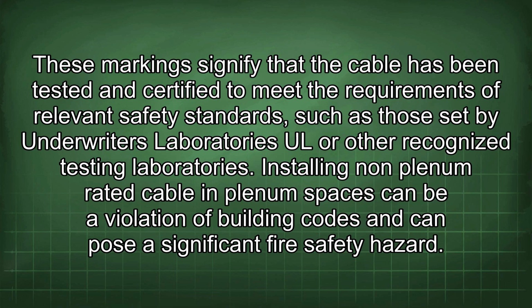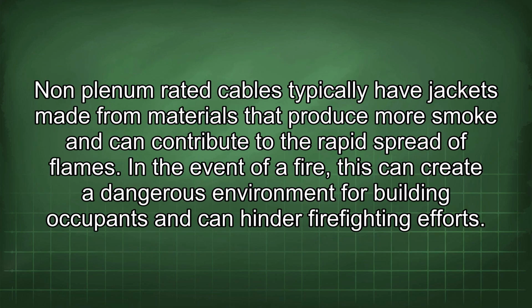Installing non-plenum rated cable in plenum spaces can be a violation of building codes and can pose a significant fire safety hazard. Non-plenum rated cables typically have jackets made from materials that produce more smoke and can contribute to the rapid spread of flames.